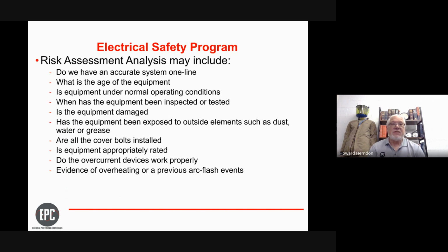So if a cover is meant to have 12 screws and it only has 4, what do you think is going to happen during an arc flash event within that equipment? That cover is actually going to come out like a blade, blowing off and hurling itself at you. So we want to make sure bolted covers are installed properly.